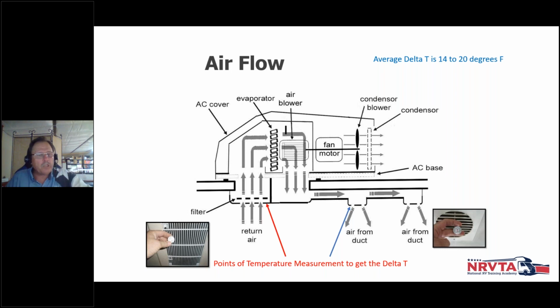Now, if you look at the picture on the left-hand side, we've taken the thermometer and inserted it in the filter. What we're measuring there is the airflow, the air temperature that's flowing through. Typically we'll fire up this air conditioner and let it run 15 or 20 minutes to where it's really circulating that refrigerant. Then we put our thermometer in there and leave it in that filter, just sticking up in there. The tip of that thermometer is measuring the temperature of the air.